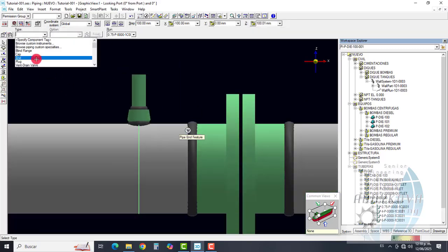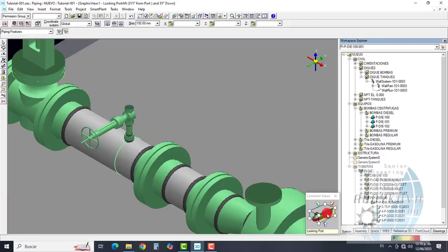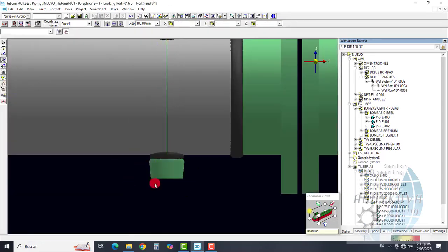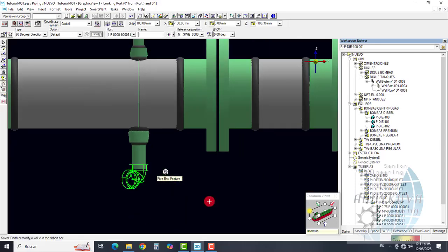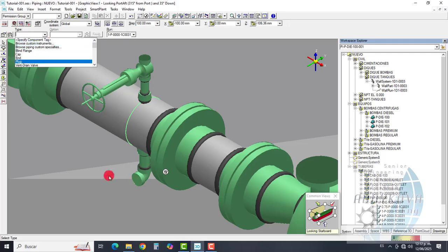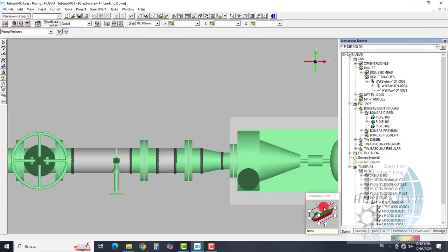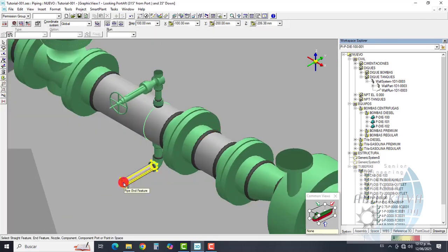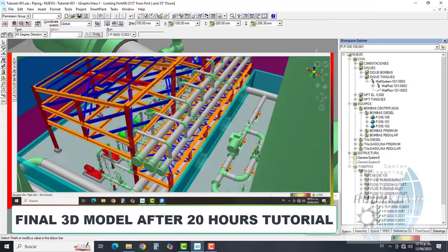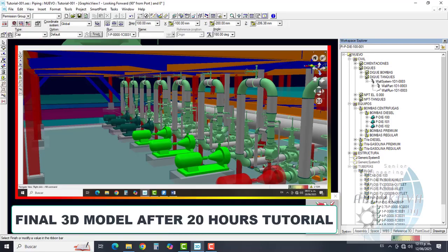Modeling of pipelines is aided by the piping specification, which limits and sometimes automatically selects piping parts. Within a particular design context of pipeline service, the specification author makes decisions in advance relating to both allowed parts and requirements for the parts that may be used in that service. Limiting the selection of parts through use of a piping specification helps the designer by eliminating the need to make decisions related to the applicability, cost, procurement, and safety of particular parts within particular pipeline services.